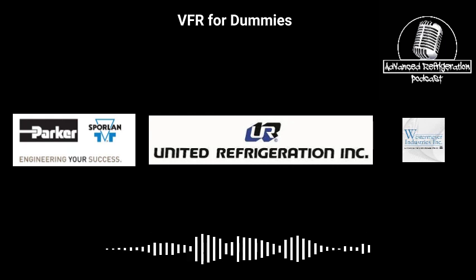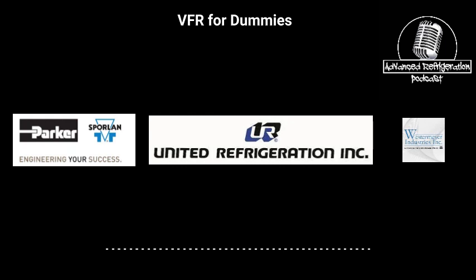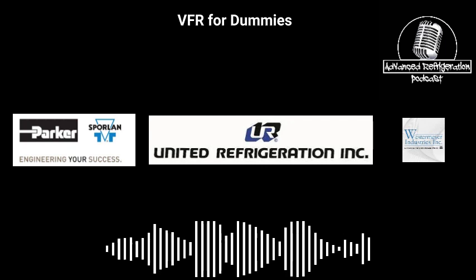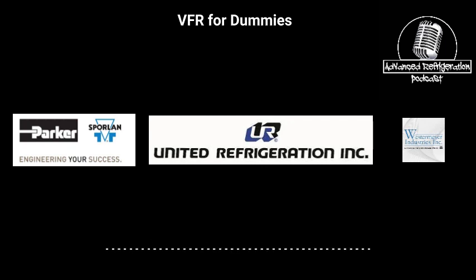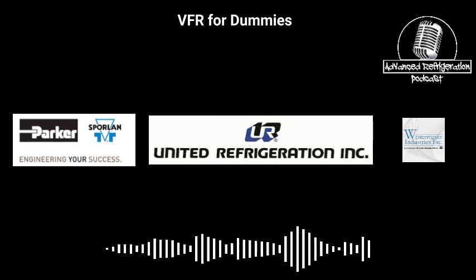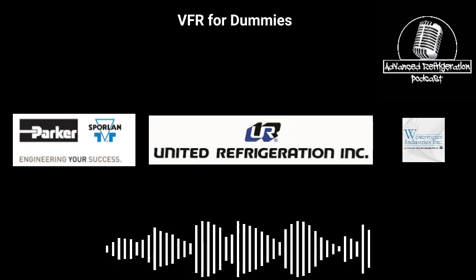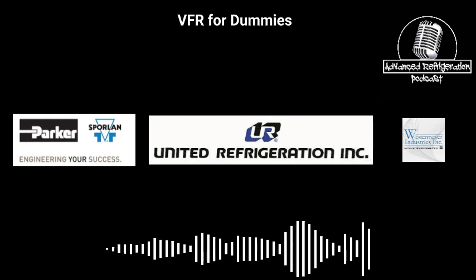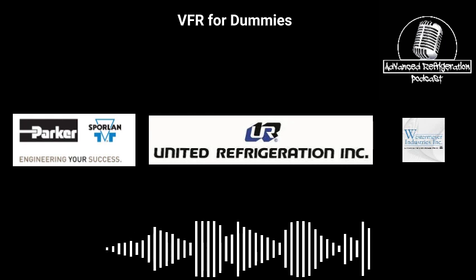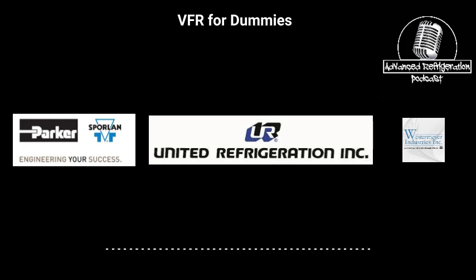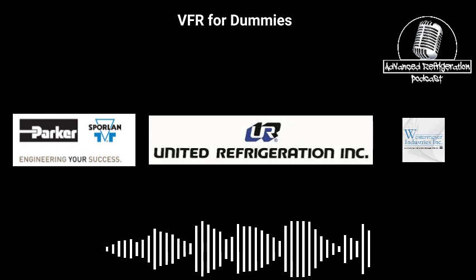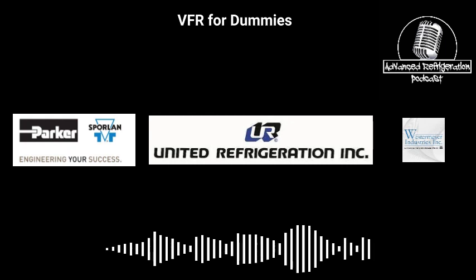Let's get down to an even better picture. All right, so here's a broken down flow diagram. This is a single compressor. Let's find the dual. There it is. This is saying it's cooling operation, single or 2 compressors, single module. You can see we have basically two suction lines coming in, hitting this one 4-way into the accumulator, into the compressors. Discharge gas is leaving the compressor, going into the outdoor coils, the upper and lower. We could talk about this one later, but it's hitting these 2 coils, shedding some heat, and then sending the liquid out to the system for regular cooling operation.